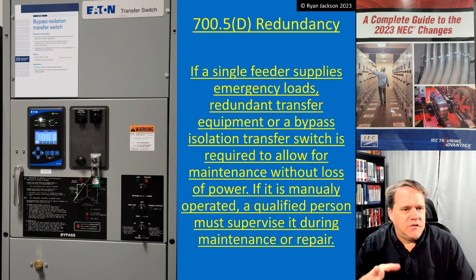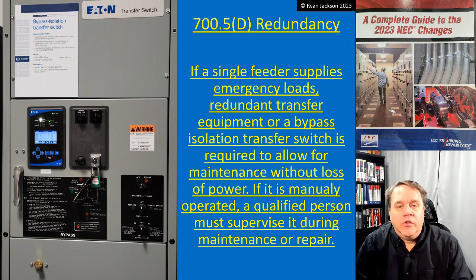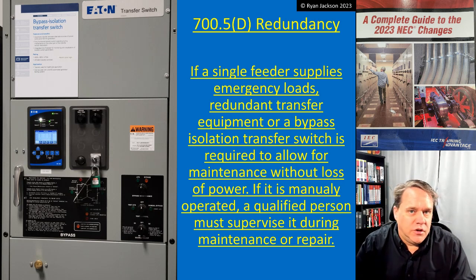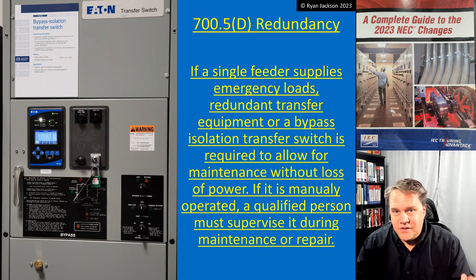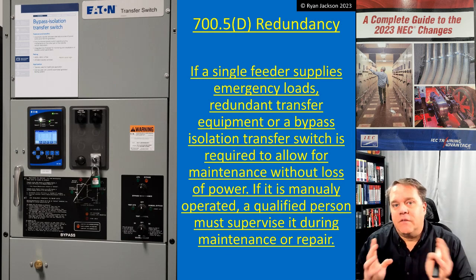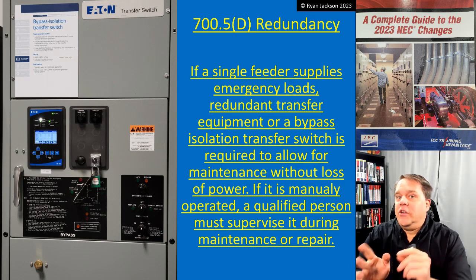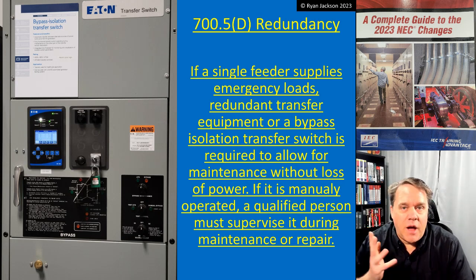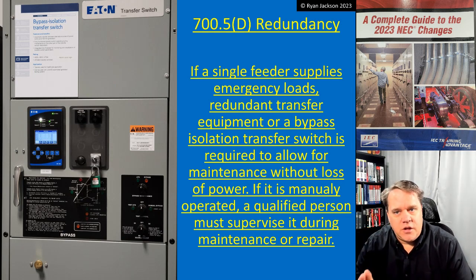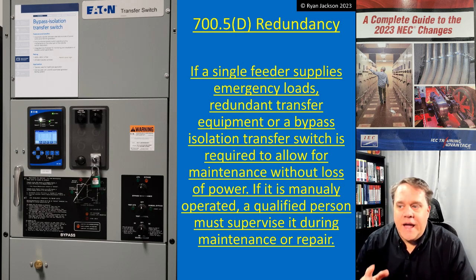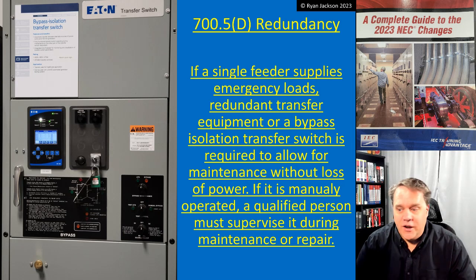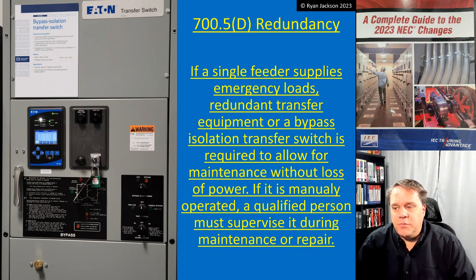This is kind of similar because transfer switches often will need maintenance as well. For the same reason, if I'm maintaining my transfer switch when the utility loses power, we can't risk the lives of all the building occupants. We have to have redundant transfer equipment, or what the code is really nudging you toward: a bypass isolation transfer switch. It allows you to maintain the transfer switch without taking it offline or doing it unsafely — working on a live transfer switch would violate OSHA, NFPA 70E, and just be a bad idea.